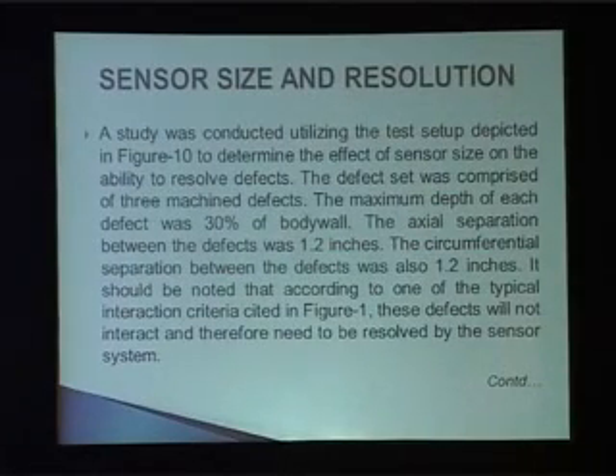Now, sensor size, I'll just spend a couple of minutes on this. A study was conducted utilizing the test setup depicted in figure 10 to determine the effect of sensor size on the ability to resolve the defect. The defect set was comprised of 3 machined defects. The maximum depth of each defect was 30% of the body wall. The axial separation between the defects was 1.2 inches. The circumferential separation between the defects was also 1.2 inches. Subsequent slide will show what is the importance of this 1.2 inch. It should be noted that according to one of the typical interaction criteria cited in figure 1, these defects will not interact and therefore need to be resolved by the sensor system.